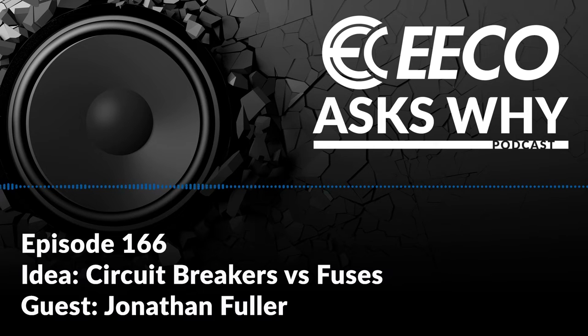Right, right. And with fuses, I think the one takeaway that hopefully our listeners are getting is that not all 30 amp fuses are created equally, right? They are different, and you potentially could damage your equipment if you don't have the right fuses. I'm even thinking of drive fuses protecting a variable frequency drive. There are special high speed type fuses in place to protect that special electronic equipment, right? Right. And just like with circuit breakers, you have some fuses that only work in AC, some fuses that only work on DC. That's going to be a common characteristic between breakers and fuses. So it's all about selecting the right fuse for your application or the right breaker for your application.